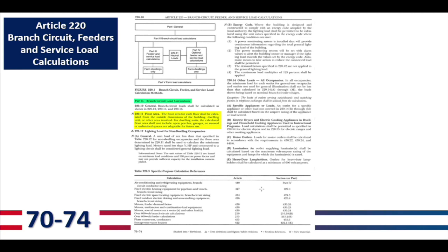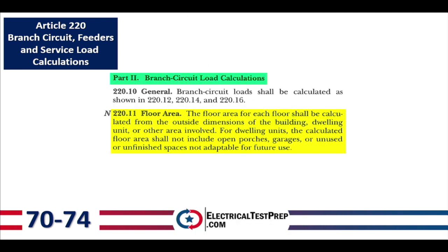Section 220.11, Floor Area. The floor area for each floor shall be calculated from the outside dimensions of the building, dwelling unit, or other area involved. For dwelling units, the calculated floor area shall not include open porches, garages, or unused or unfinished spaces not adaptable for future use.